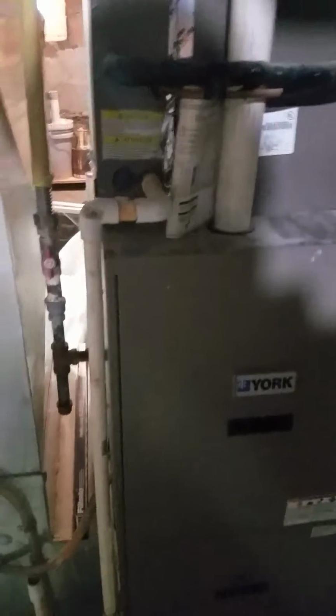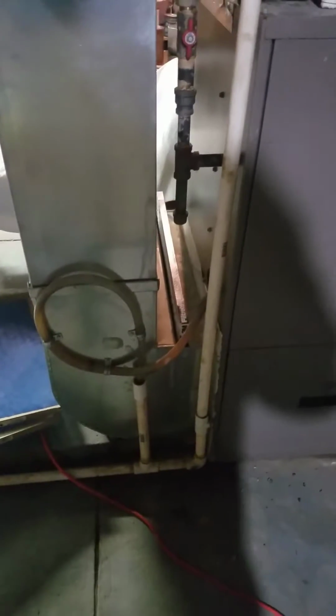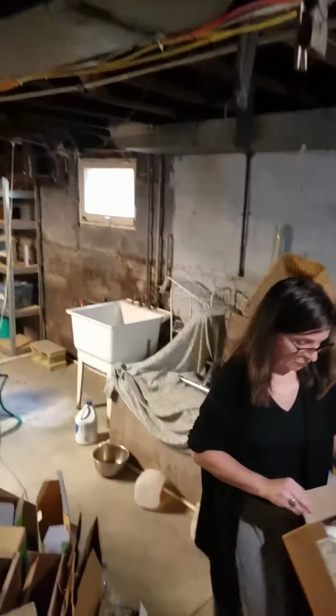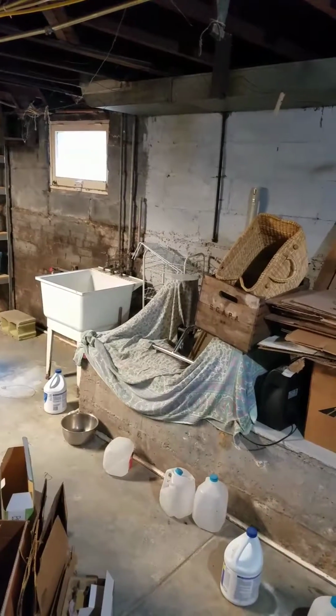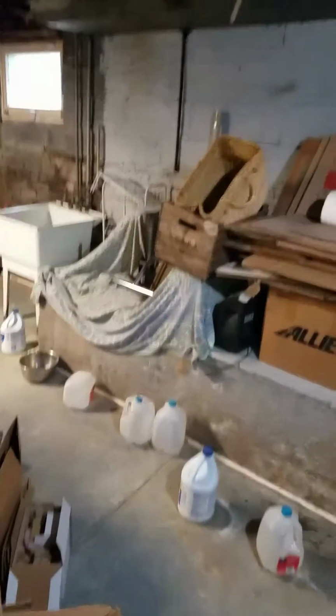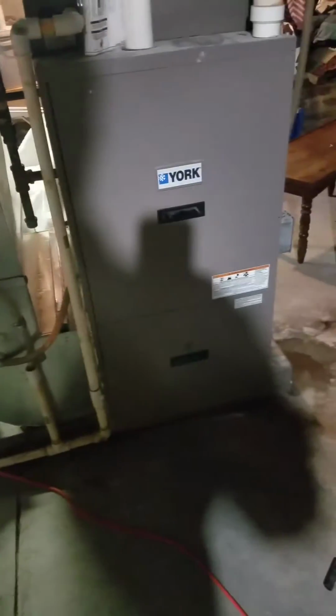What is needed on this, we're contemplating on just replacing the furnace, and we have a condensate line that's about 100 feet long, goes all over the basement, and I would like to get rid of this, put a condensate pump on it, and run about 40 foot of tubing right over there and into that sink right over there that she's got sitting there, so you can run it up across the ductwork and down into the sink. So that needs to be addressed to get that up off the floor.